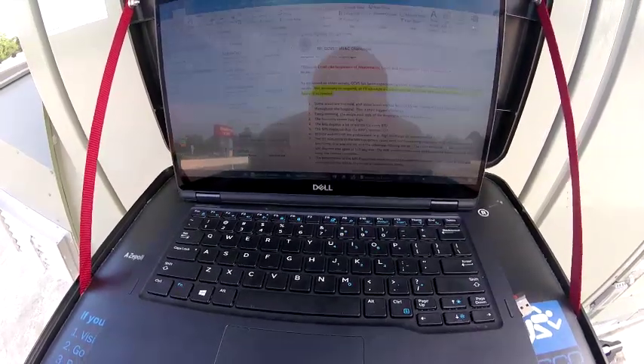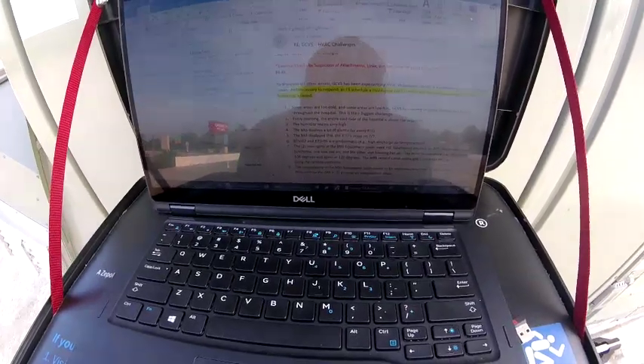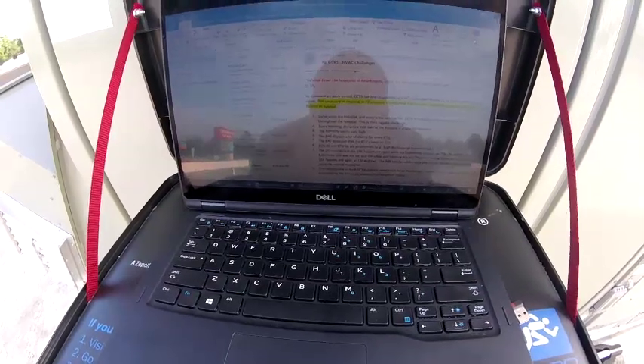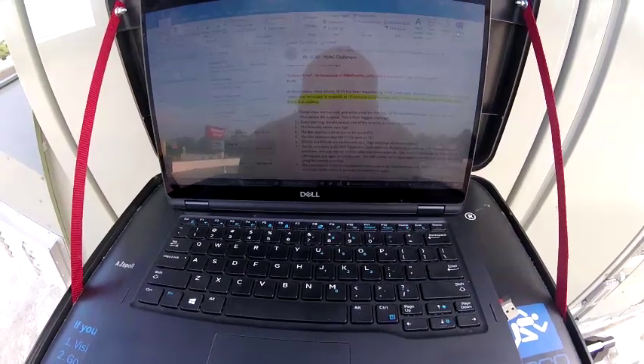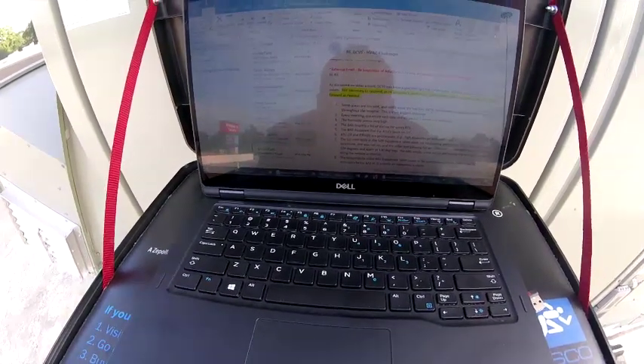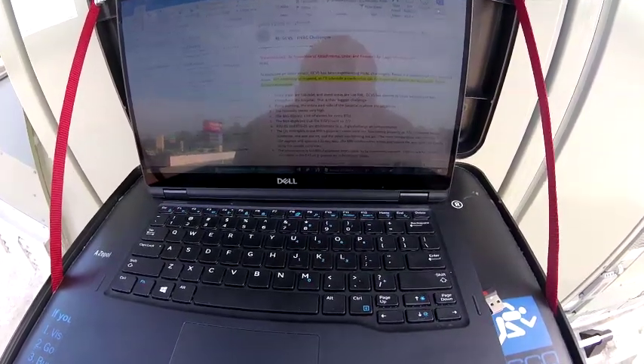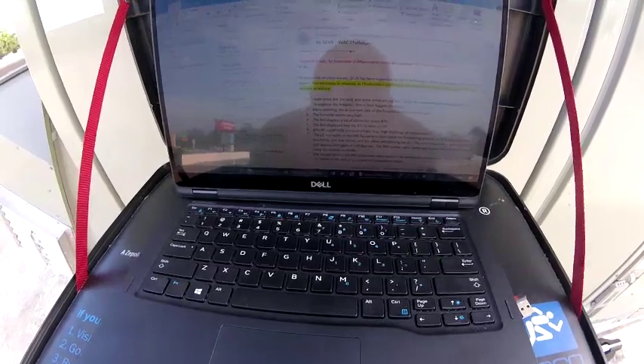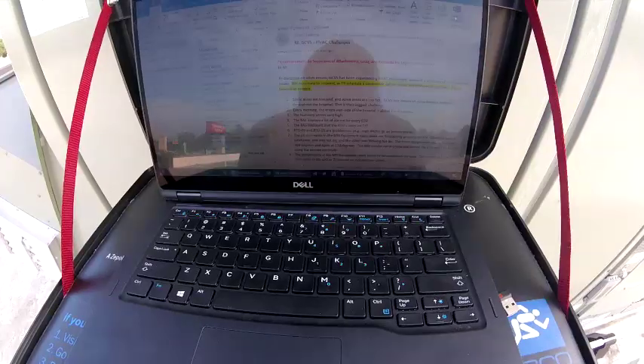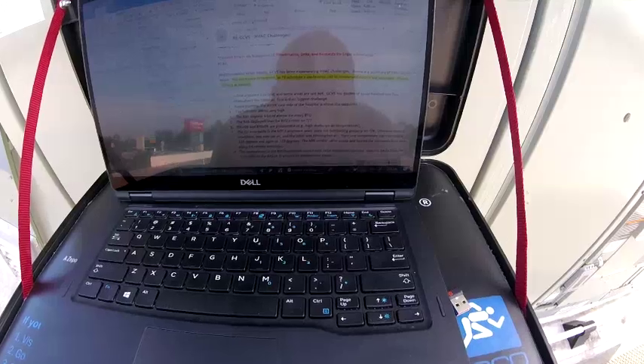Number three, the humidity seems very high. Number four, the BAS displays a lot of alarms for every RTU. Number five, the BAS displays that the RTUs reset on 7/7. Number six, RTU 2 and RTU 5 are problematic. High discharge air temperatures. The two mini splits in the MRI equipment room are not functioning properly on 7/9.